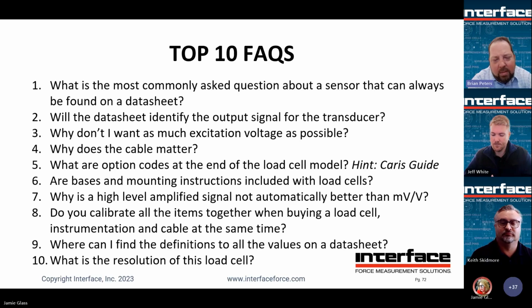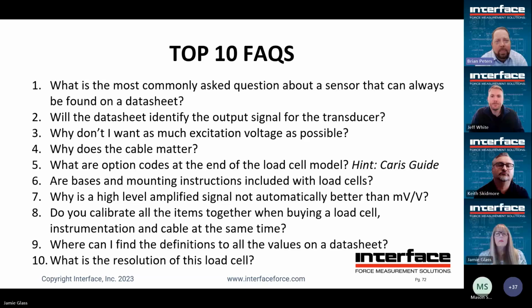But general rule of thumb in terms of sizing a load cell for a given force level is try to stay above 1 in 30,000. Again, even though the load cell will respond infinitely, that's generally a decent area. Again, assuming you're using some good quality components and you've taken system level considerations into account. So resolution almost always limited by the instrument.